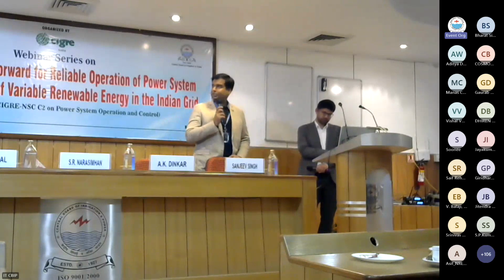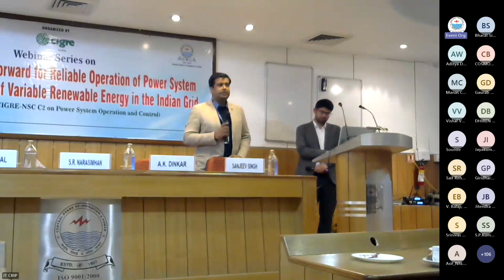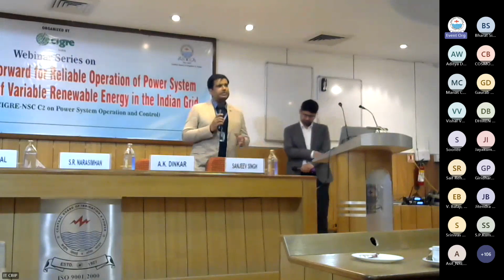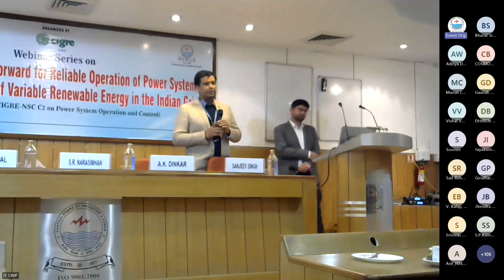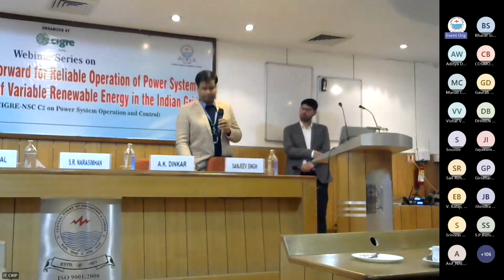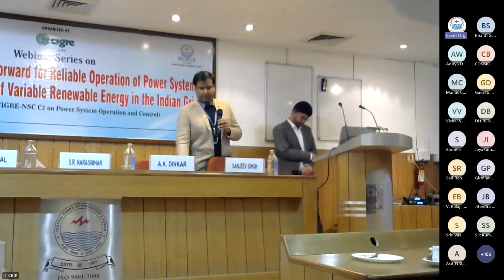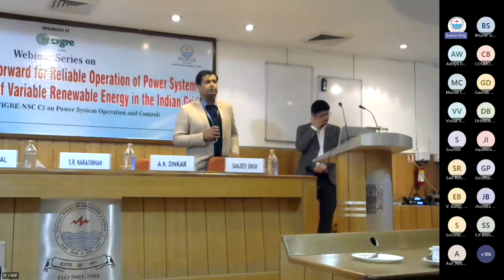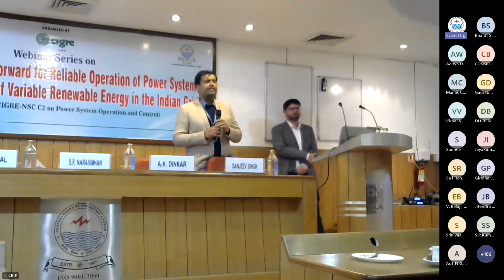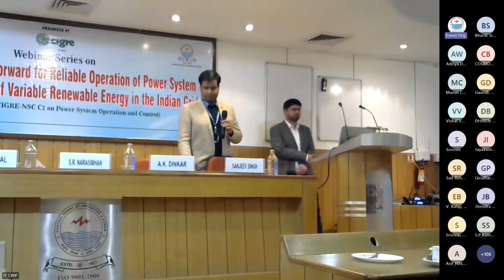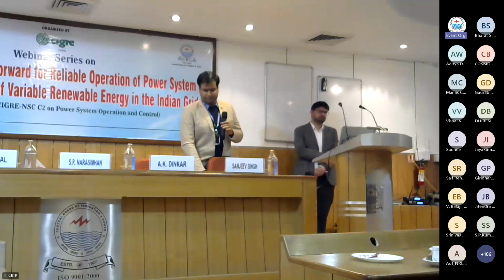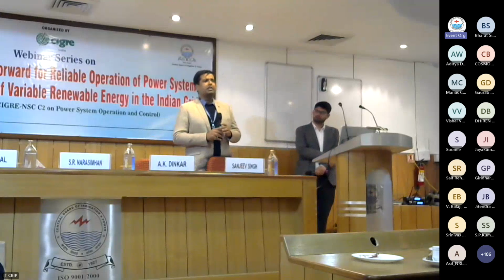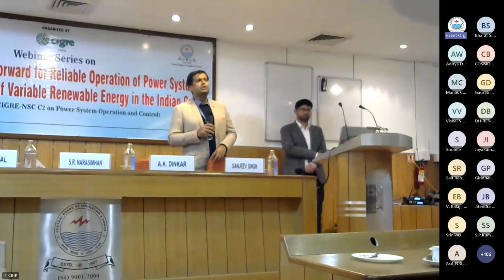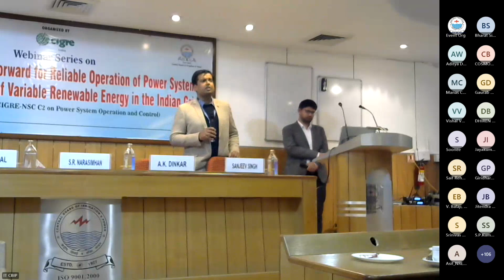Yes, good question. Certainly, the power quality is being measured. It has to be measured as per the CEA standards. You very well mentioned that the THD, total harmonic distortion, limit should be within 5%, say for load. So different scenarios are possible. Sometimes wind can be high, sometimes it can be low, sometimes some other nearby generator will be there, and sometimes the load will be having a different set of things.